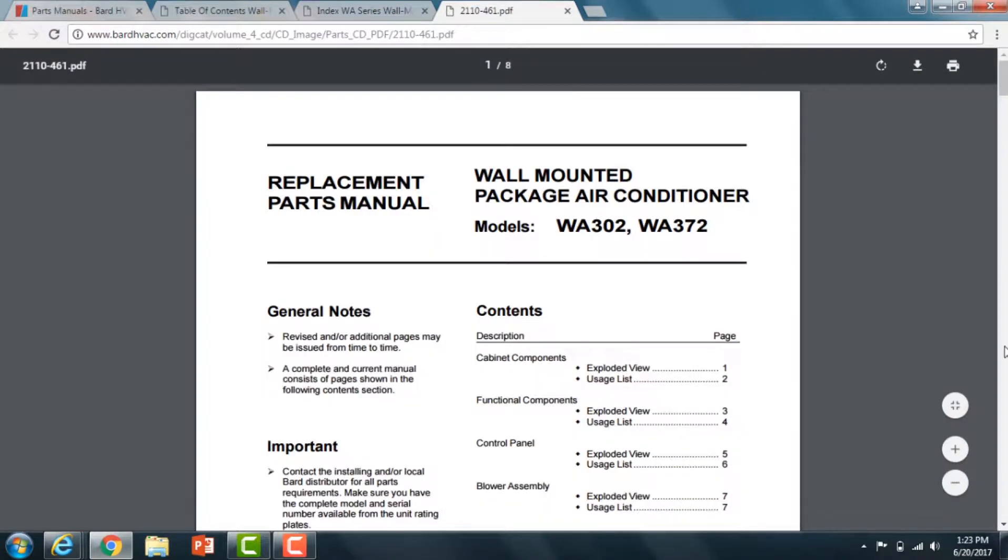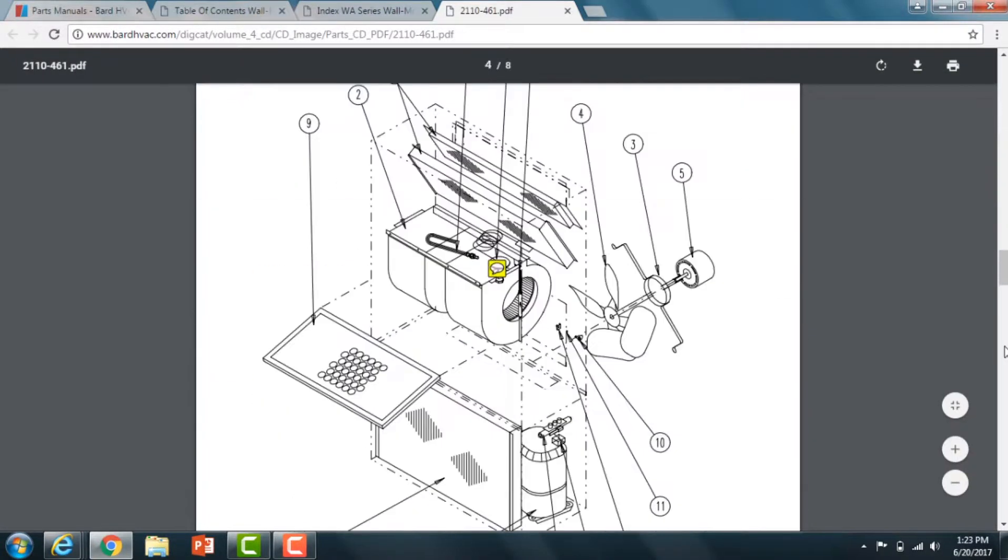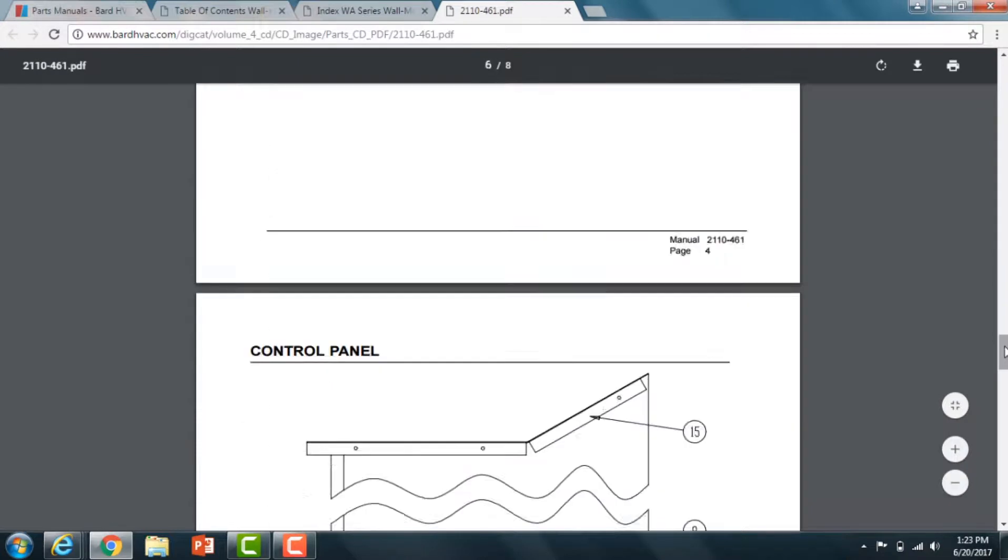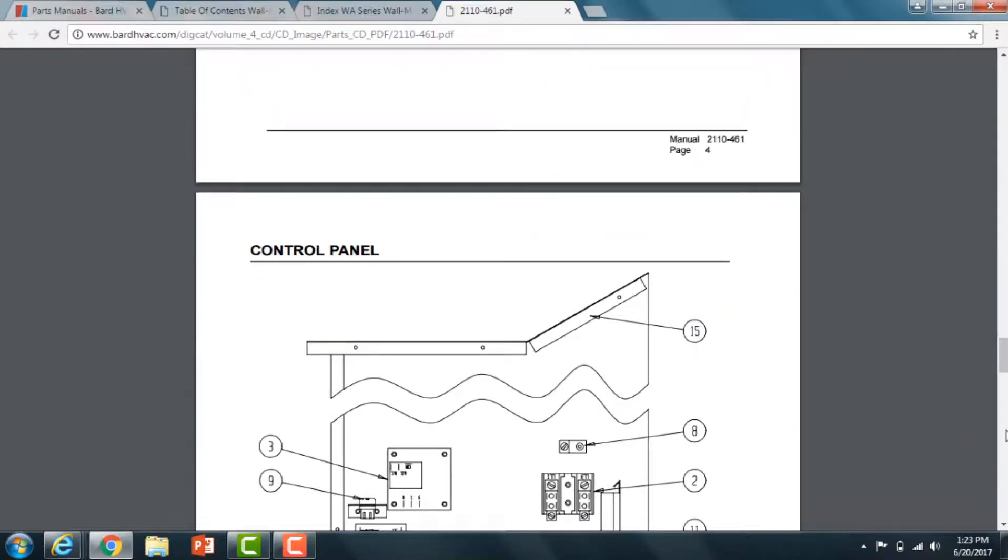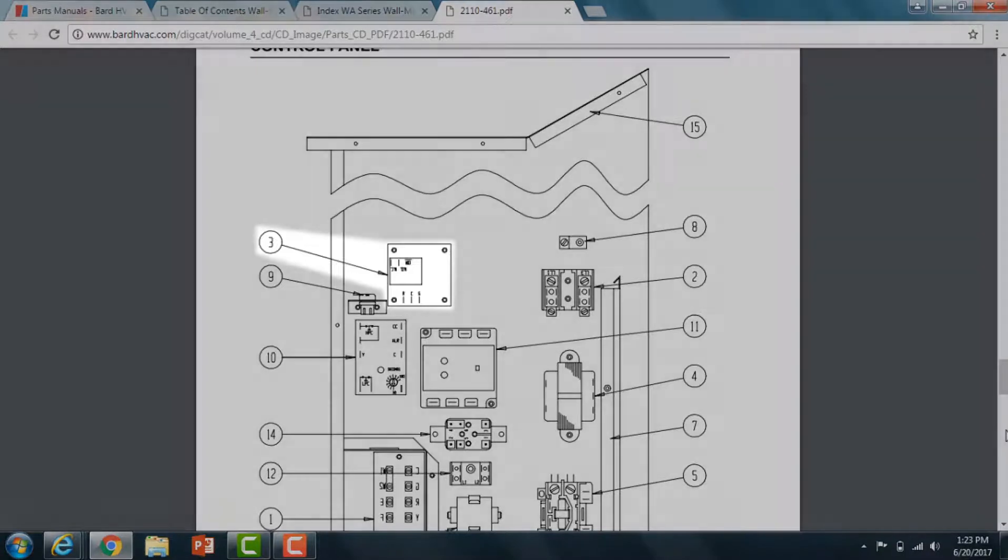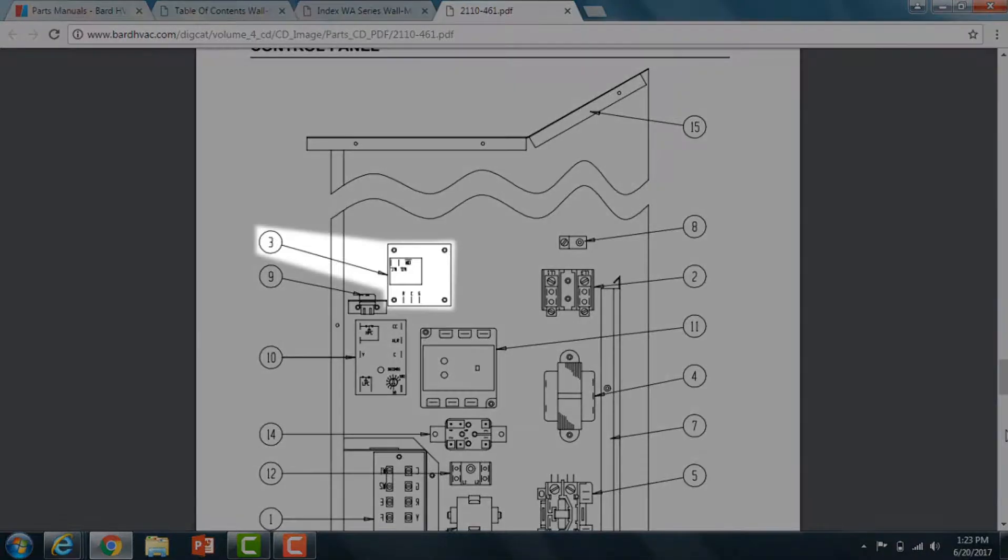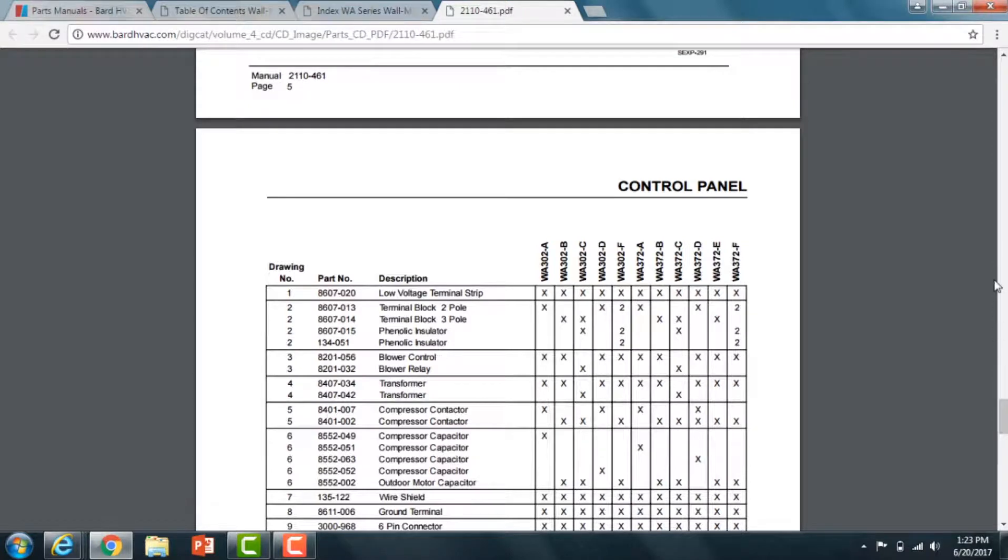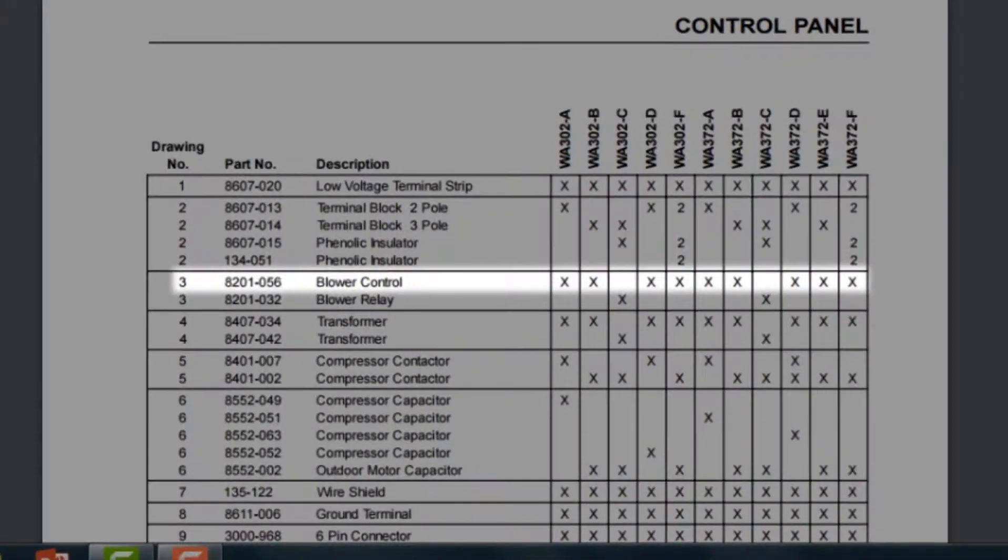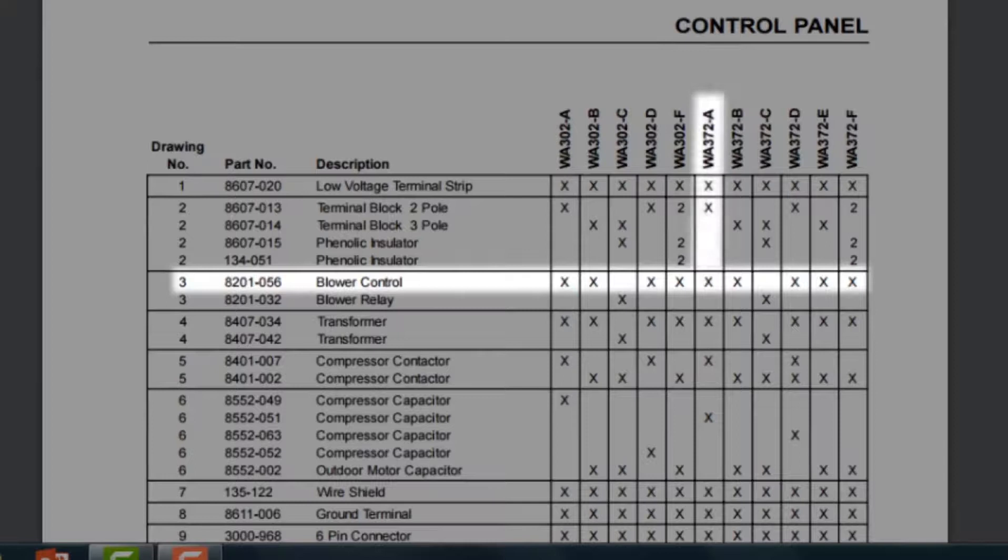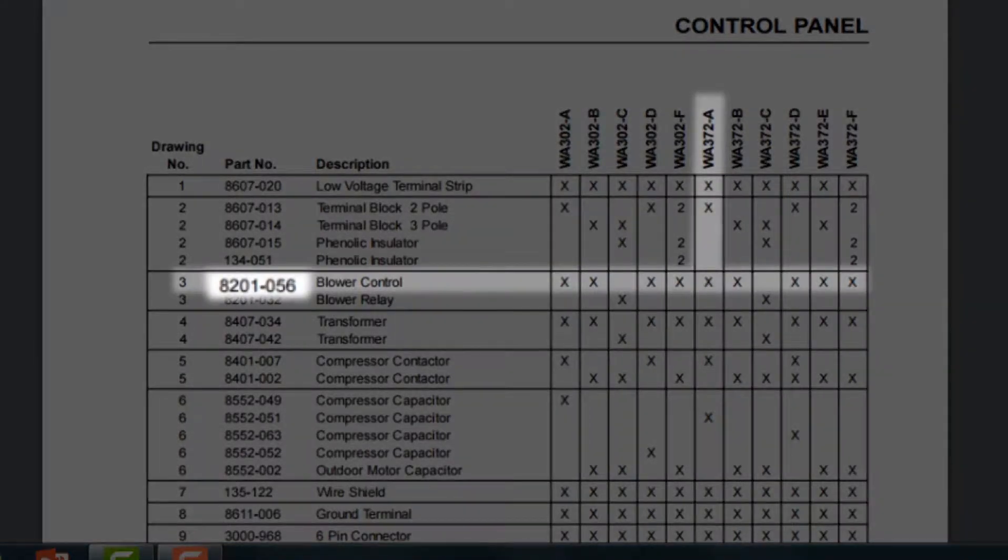In the parts manual, it's going to show sheet metal first, then functional components, the electrical control panel, and then the blower assembly breakdown. What you do is you find your particular part in the picture, find the balloon, go to the chart which is the next page. That's going to give you the actual part number. Find your model number and the voltage code, and scroll down the column to get to that particular balloon. That's your part number.